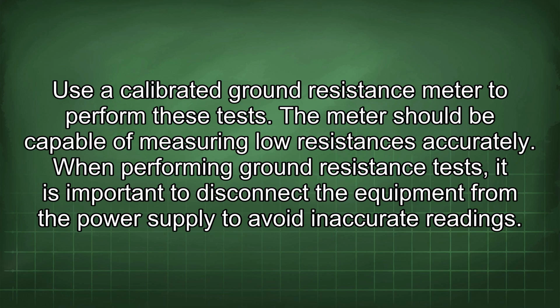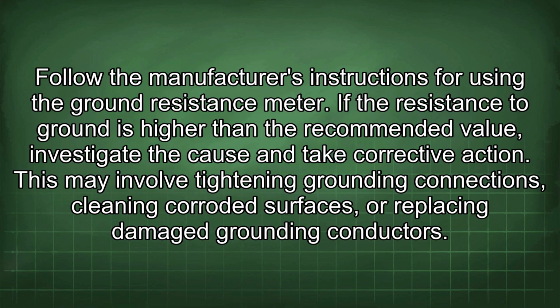When performing ground resistance tests, it is important to disconnect the equipment from the power supply to avoid inaccurate readings. Follow the manufacturer's instructions for using the ground resistance meter. If the resistance to ground is higher than the recommended value, investigate the cause and take corrective action. This may involve tightening grounding connections, cleaning corroded surfaces, or replacing damaged grounding conductors.